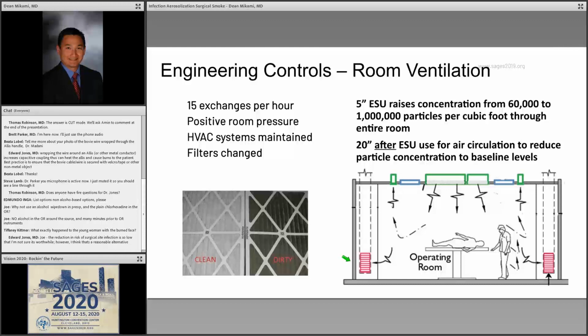So most ORs, if not every OR, are designed to be positive pressure, meaning that we want to keep the dust from entering our doors, right? So the room is positive pressured, so it pushes air out of the room to prevent dust from being suctioned into our OR. Unfortunately, if we're operating on a COVID patient or a patient that has an infection, we don't have that negative pressure suctioning the virus out of the room. We rely on HEPA filters for this. So best practice is to intubate our patients in a negative pressure room and bring them to a positive pressure room after.